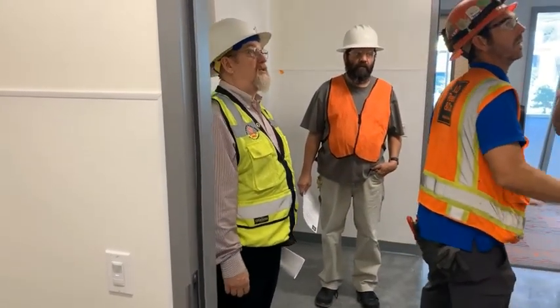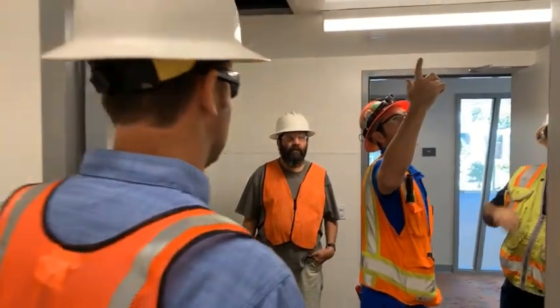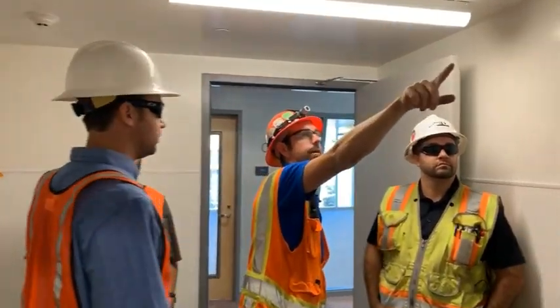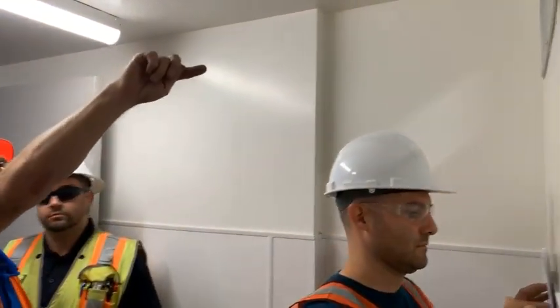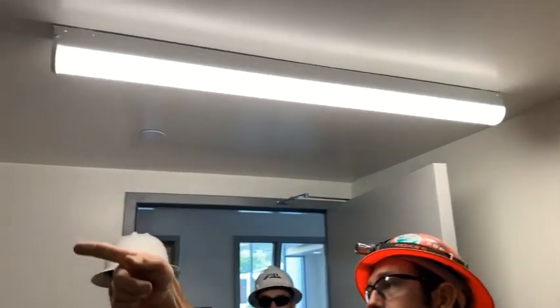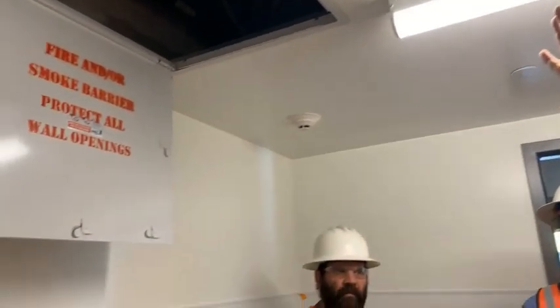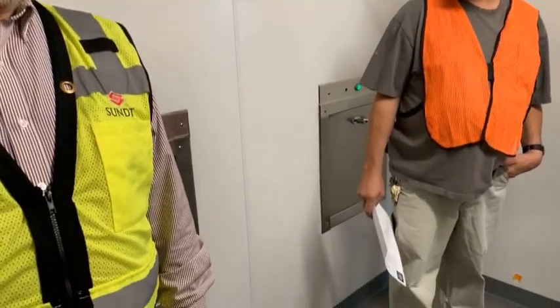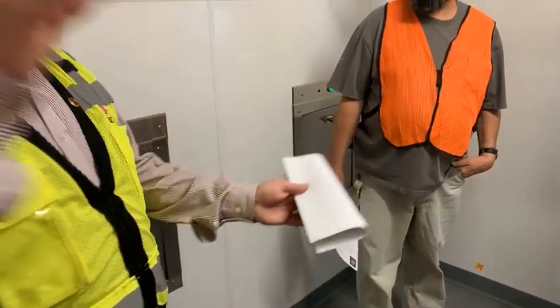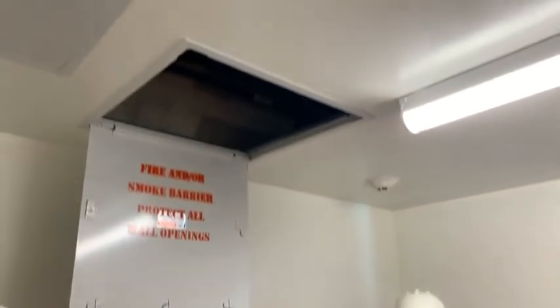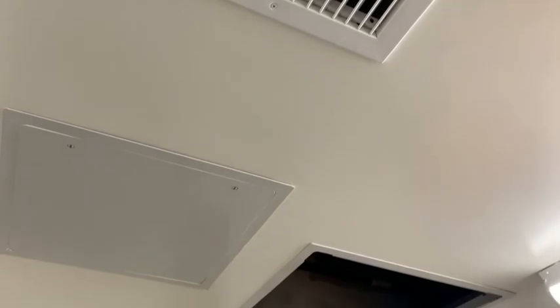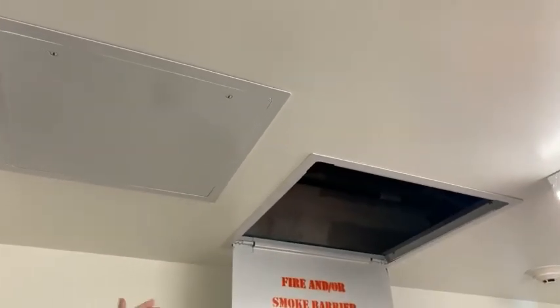This room right here is gonna be transferred from outside out there. There's backdraft dampers you can see through the opening. We're gonna draw air through here and out. The air for the trash room goes into the trash chute shaft. There's an exhaust fan on the roof that draws air through the shaft. So all the air will come in through here, into this louver up here, or this grill, excuse me, into the shaft. Yeah, there's a fan, they'll suck it out into the shaft, and there's another fan. Another fan will put it up over there.